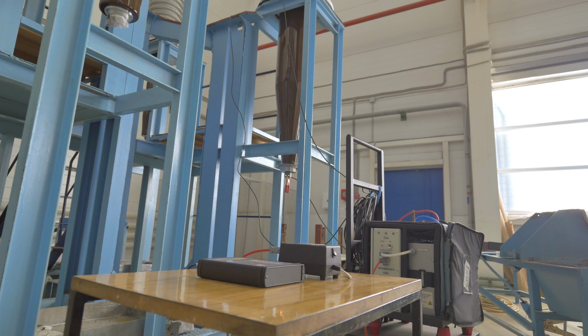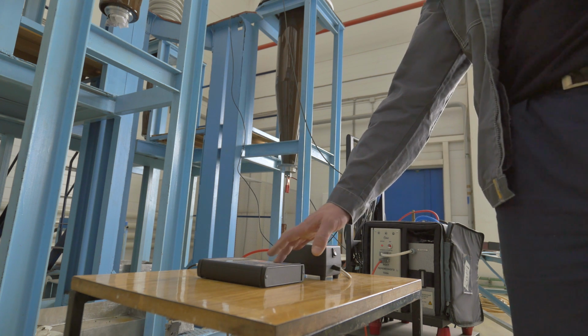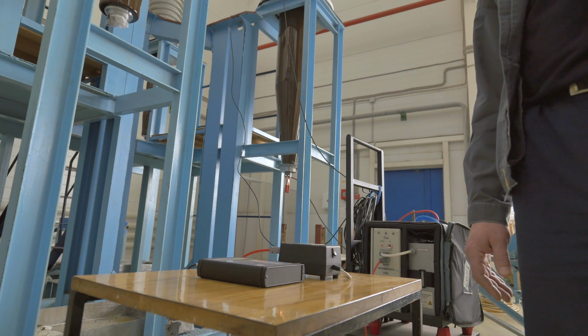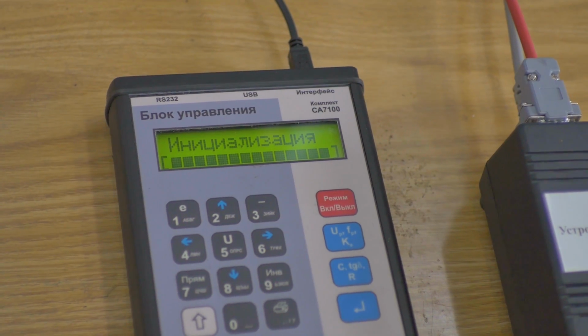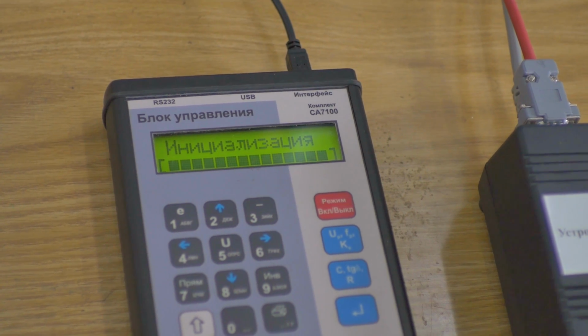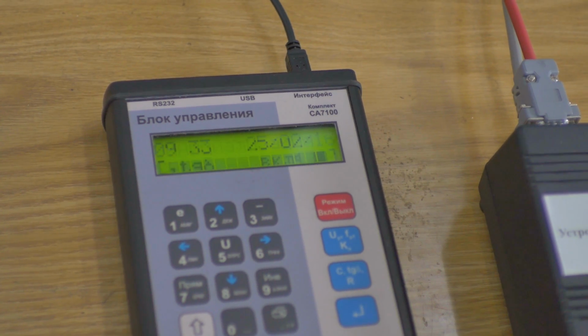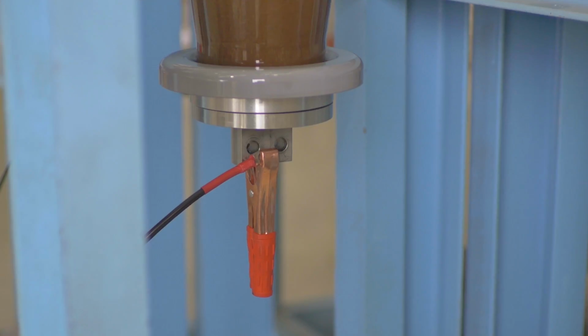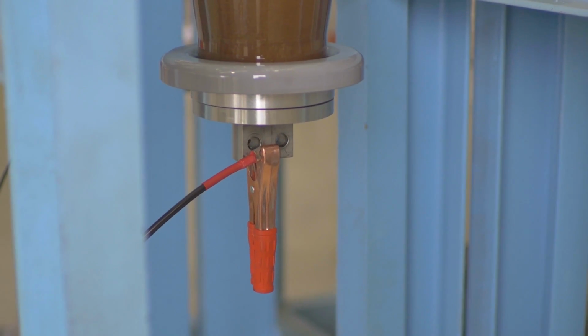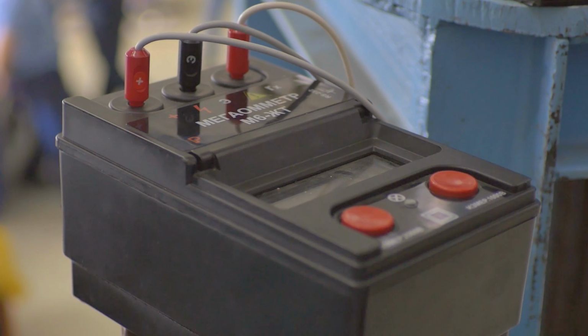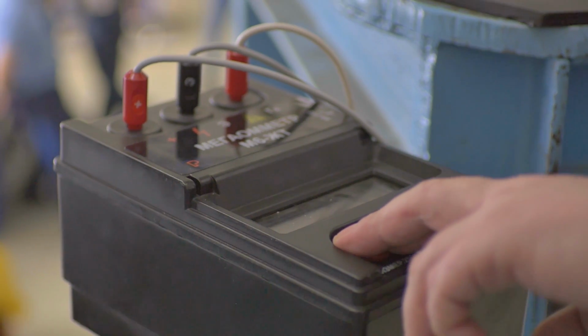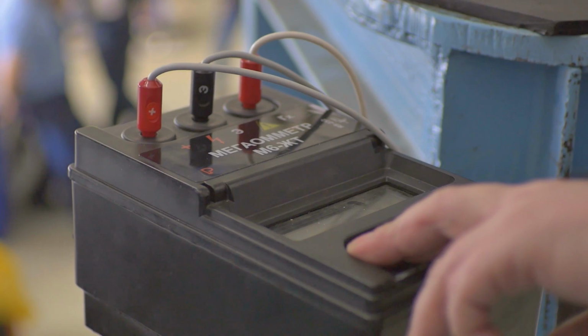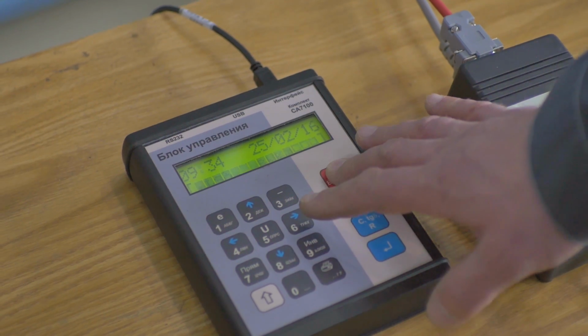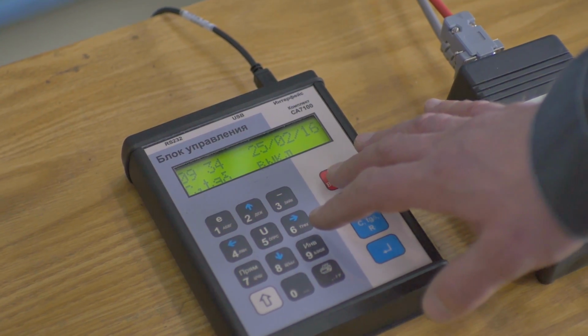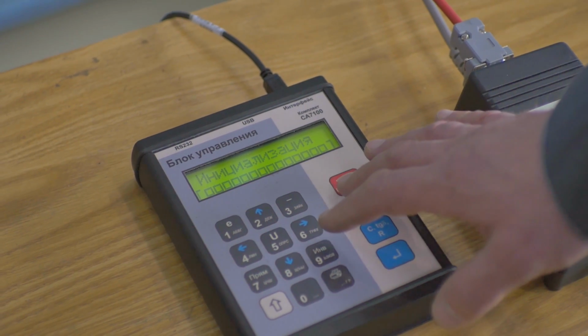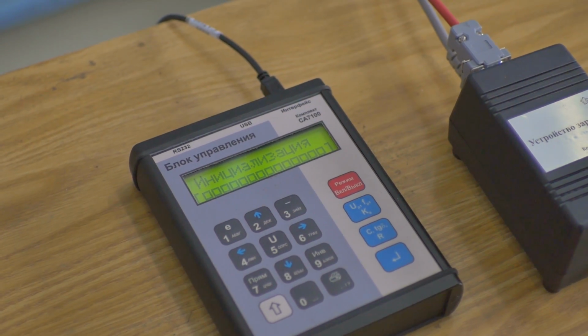Humidity, weather conditions and other factors also influence dielectric loss tangent measurement results. Correct measurements and results evaluation allow for a quality bushing operation throughout its operation life. Based on years of RIP bushings production experience and field operation data, we can say that a minute increase, less than 2/10, of the dielectric loss tangent against values shown at the acceptance tests at the manufacturing plant is not a symptom of damaged insulation.